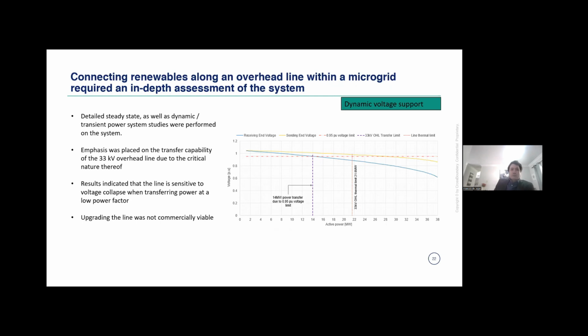Like I said, one of the more novel approaches that we had to apply on the system was managing the flow of power across the 33 kV distribution system that I showed at the start of the presentation. If you've worked on distribution systems before, you would understand that there's a thermal limitation when it comes to the actual conductor ratings, but there's also typically something more critical, which is the voltage collapse point, essentially caused by the flow of reactive power through a reactance. In other words, if we try and push reactive power across an overhead line with more inductive capacity than capacitance, we end up with a large voltage drop, which ends up collapsing the system if we exceed the stability limits.